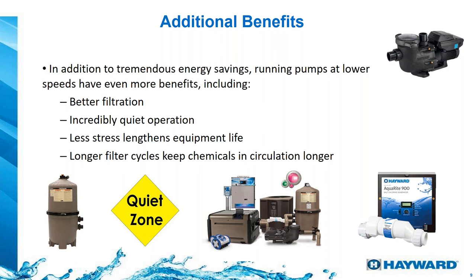By doing this, we have more time for chlorination and more time for the water to move through the pool for filtration. We also have more time to produce heat when we have a heater. Remember, if we don't have flow, heaters will not produce heat and chlorinators will not produce chlorine. And since the water is not moving as fast, our equipment will last longer — for example, a cartridge filter element will last much longer by reducing the speed.